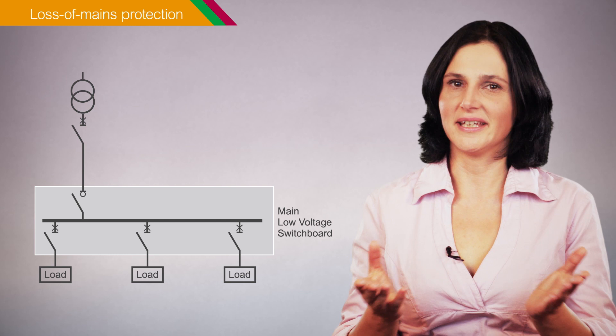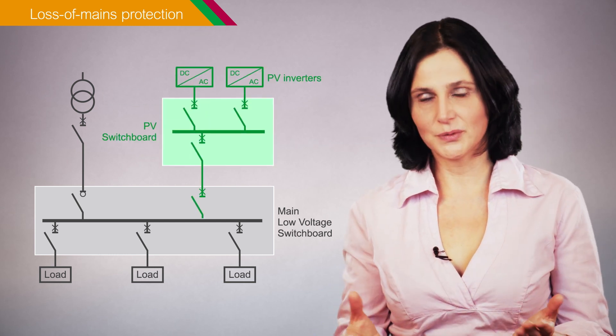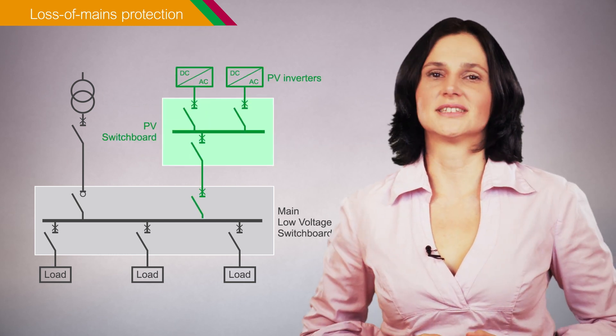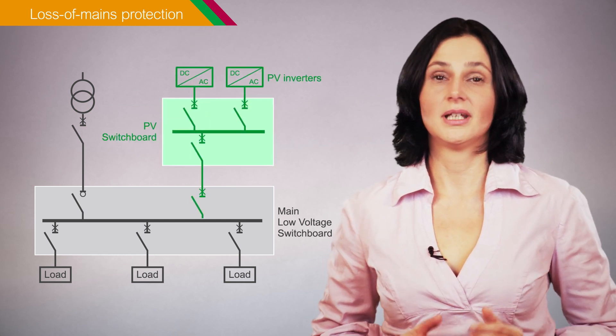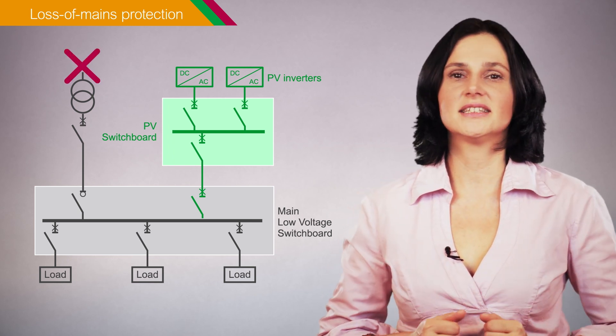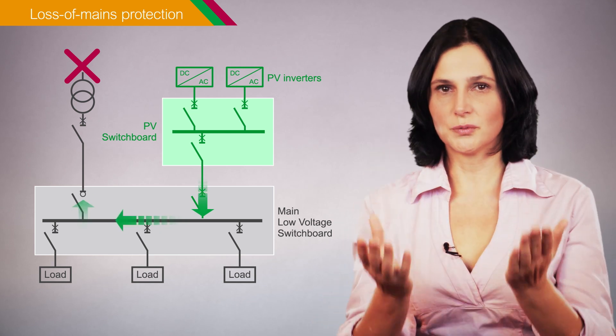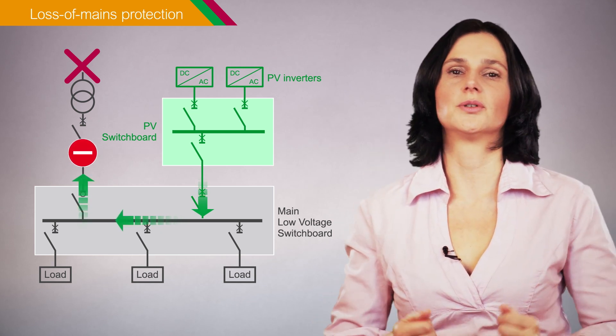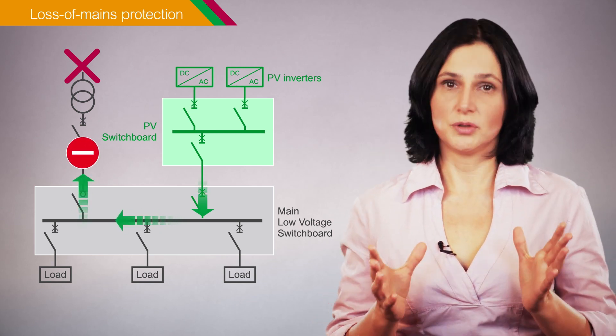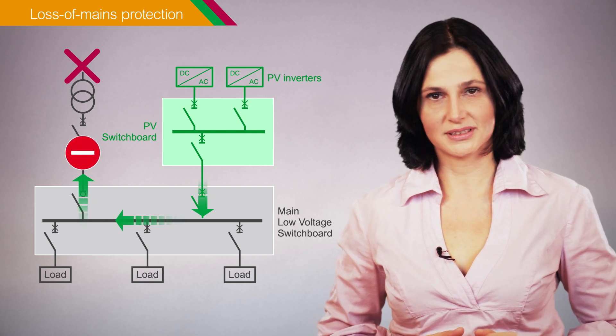Loss of mains protection is required by grid codes and by energy distributors for installations with photovoltaic self-consumption. This protection guarantees that in case of utility supply outage, the installation will not energize the distribution network, which could compromise the safety of utility workers.